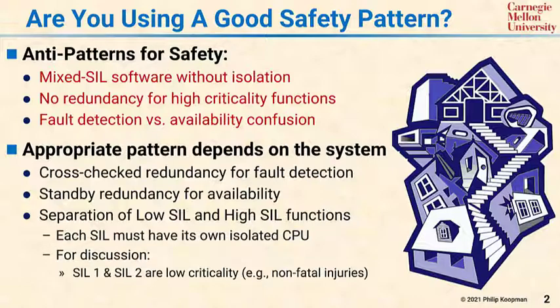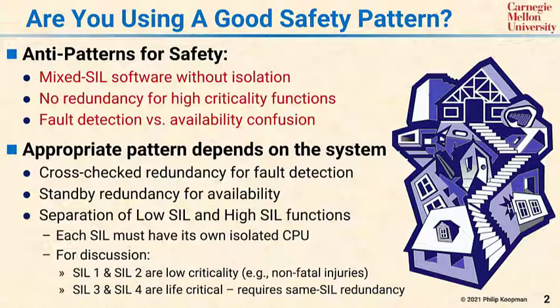For this discussion, we're going to assume that SIL 1 and SIL 2 are low criticality. SIL 1, for example, might involve minor injuries, and SIL 2 would involve major but not fatal injuries. On the other hand, SIL 3 and SIL 4 are high SIL systems with life critical applications. In SIL 3, it is possible that someone will be killed or very severely injured, and at SIL 4, it's basically a catastrophic loss.